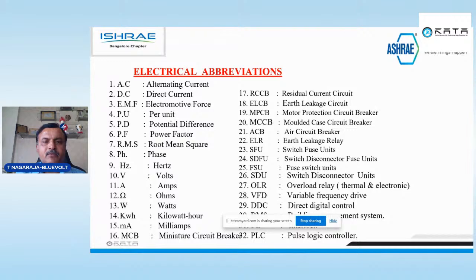So wherever the cables are running a long run, 50 meter, 100 meter, to incomer big cables, this earth leakage relay will be used on the panel incomer side. If any damage happens, immediately this leakage will show and we can take corrective actions. SFU: switch fuse units, switch disconnector fuse units, fuse switch units, switch disconnect units. Then overload relay. Thermal and electronic, both the types are there.